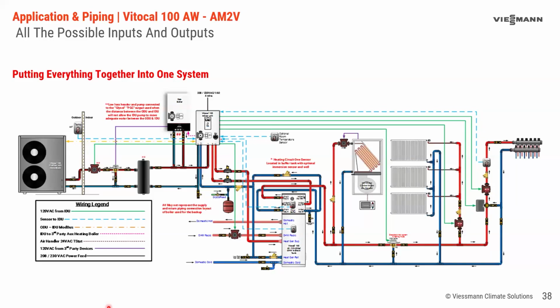So one thing I wanted to point out, something I've seen quite a bit, is your circuit one with air handler and panel rads. I know at least where I'm at, in upstate New York, we have a lot of areas with a basement air handler and an attic air handler. So just to think outside the box for everybody, that doesn't have to be panel rads. That could be two separate air handlers on that heat circuit one. I run into those systems quite a bit. It's easy ductwork for those retrofits. So keep that in mind.